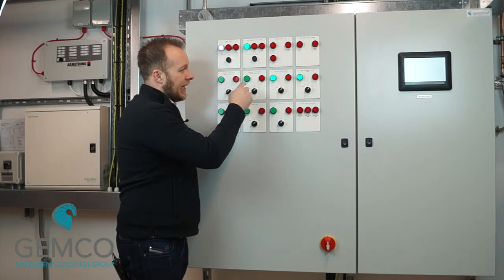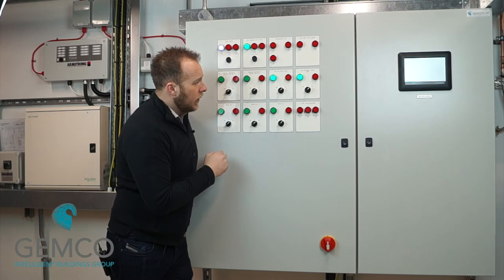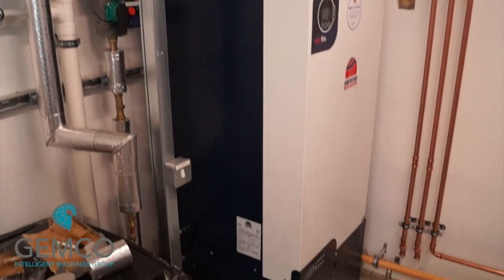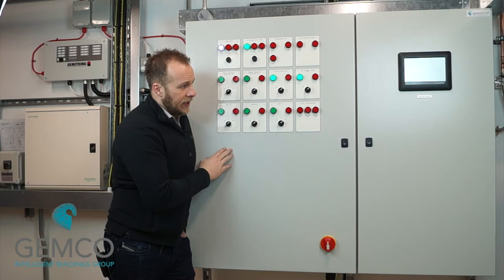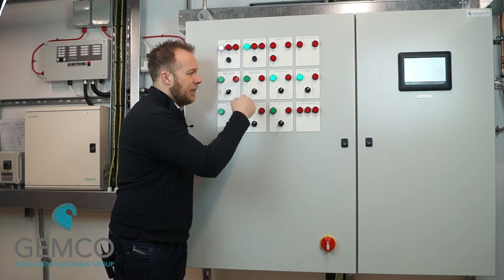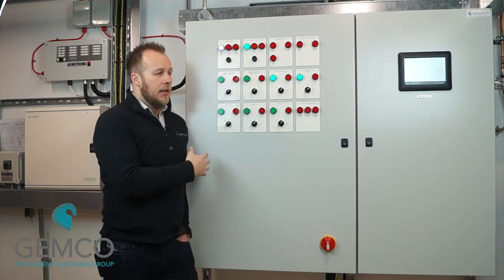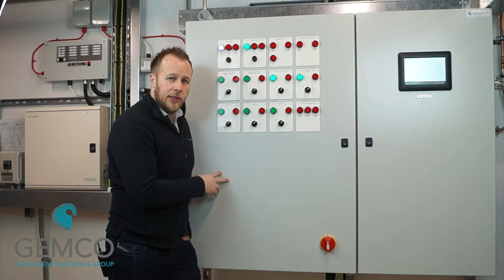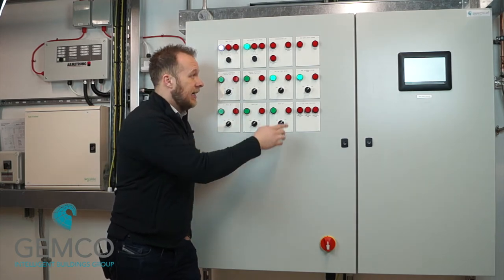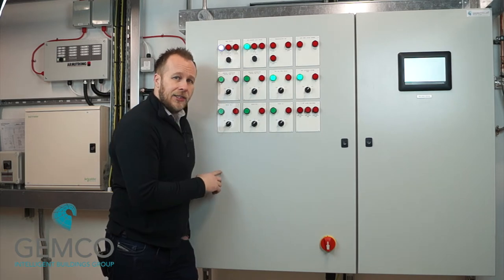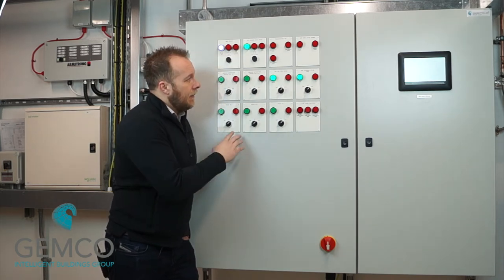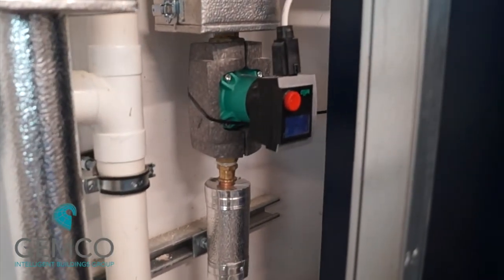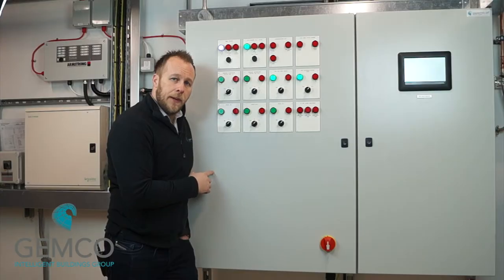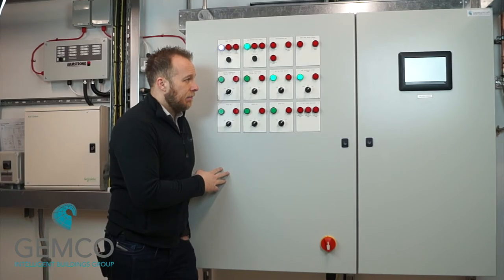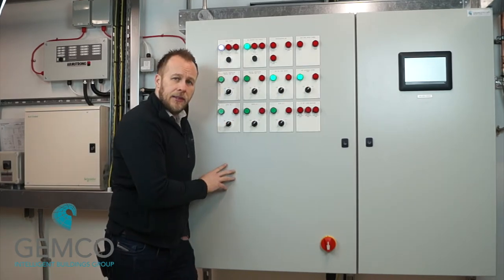And then we've got the gas-fired water heater, which has its own temperature control. So via the little stat and programmer on the heater, you'll be able to set the temperatures. We do enable the heater from here. We enable the heater from this panel under separate time switch control. Okay, and then once that's enabled, we monitor it for a lockout indication. Okay, and then the HWS secondary pump again is enabled on time switch control. It's only one single pump. Once it's enabled, then we monitor it for a trip status.